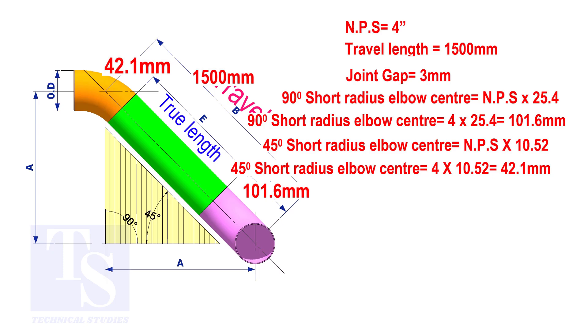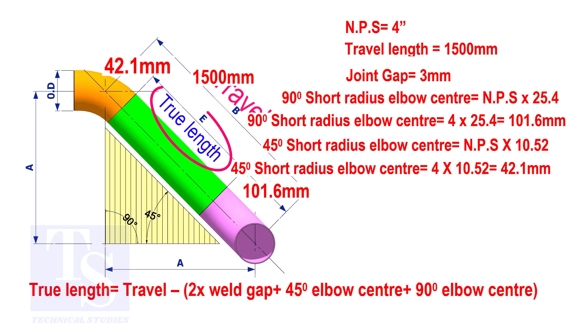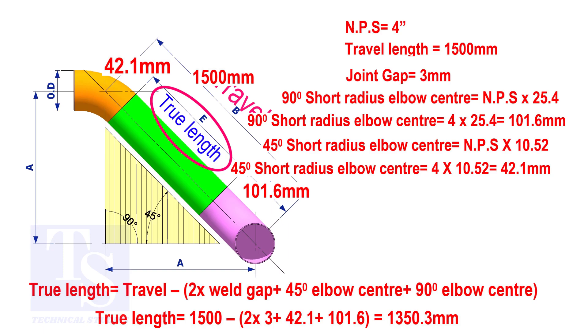To calculate the true length of the pipe, subtract two weld gaps plus both elbow centers from the travel length. The true length of the pipe is 1,350.3 millimeters.